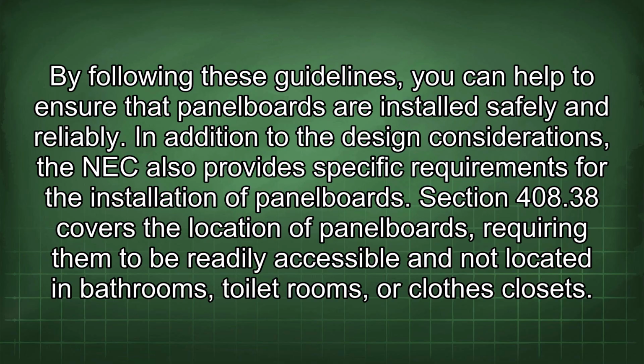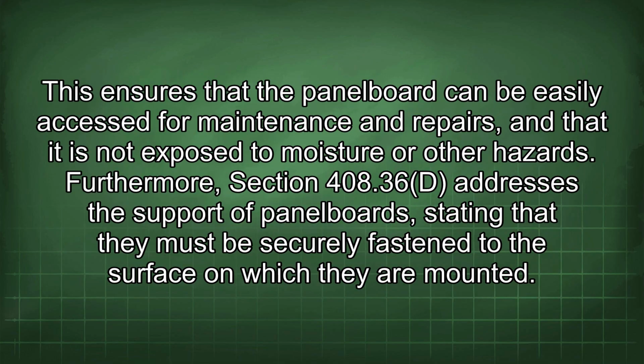In addition to the design considerations, the NEC also provides specific requirements for the installation of panel boards. Section 408.38 covers the location of panel boards, requiring them to be readily accessible and not located in bathrooms, toilet rooms, or clothes closets. This ensures that the panel board can be easily accessed for maintenance and repairs, and that it is not exposed to moisture or other hazards.